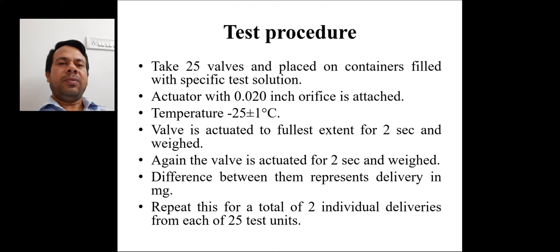Now test procedure. Take 25 valves and place on containers filled with specific test solution. Actuator with 0.02 inch orifice is attached. Temperature of 25 degrees plus minus 1 Celsius is maintained. Valve is actuated to fullest extent for 2 seconds and weighed. Again the valve is actuated for 2 seconds and weighed. Difference between them represents delivery in milligrams. Repeat this for a total of 2 individual deliveries from each of 25 test units.